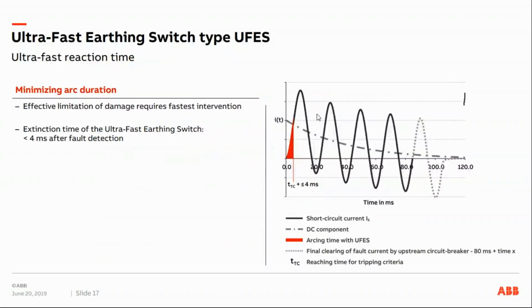Here we can see the occurrence of a short circuit fault. What we see here is that the extinction time for the UFES is even below the time at which the short circuit reaches its peak. So we have the time to reach the tripping criteria plus the 4 milliseconds after fault detection.